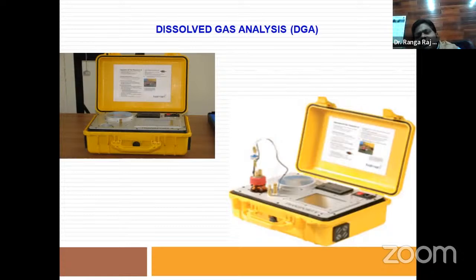If you perform only this test, that is enough to decide the health of the transformer. But the way of performing this test must be proper, because a lot of precautions have to be taken in the process of collecting the sample and putting it into the bottle. It's a very sensitive procedure.